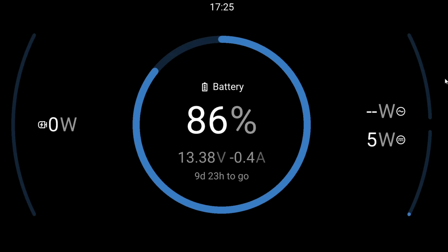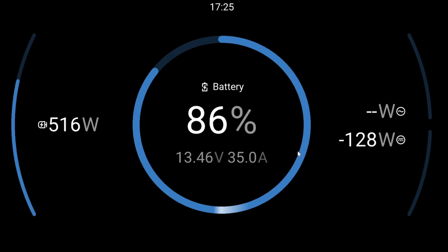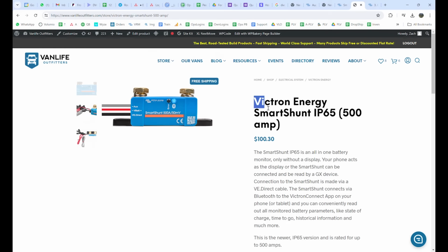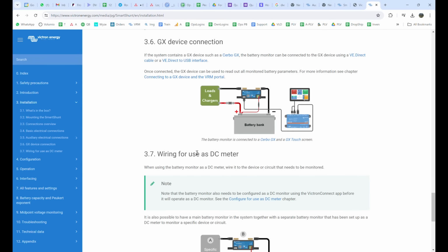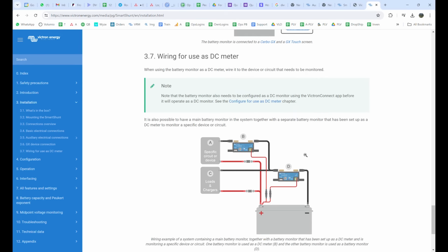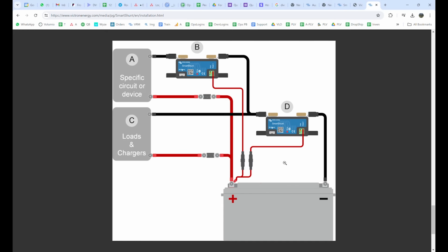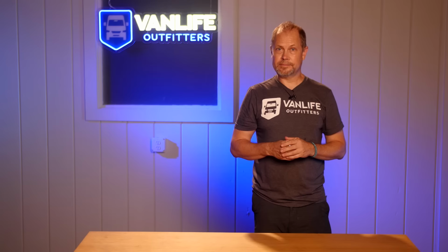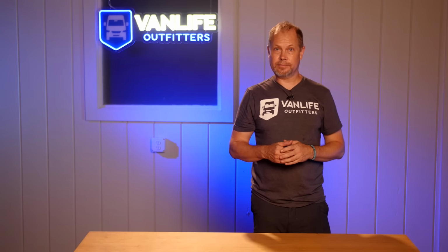What you see on the main system smart shunt is the sum of all incoming current from the chargers minus these little DC loads. If you did want to use, let's say, another smart shunt as a DC meter so that you could account for those kinds of loads in the total max current calculations, you could add a second or third or fourth smart shunt as a DC meter, and we'll link to the manual below that has details on how to accomplish that.